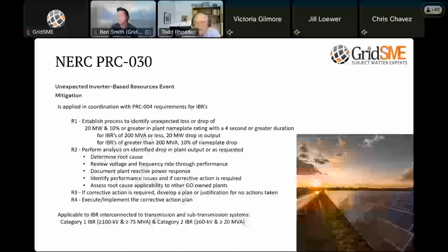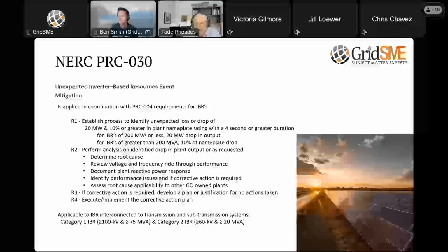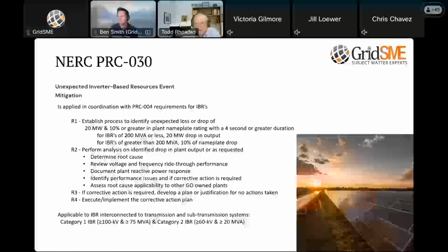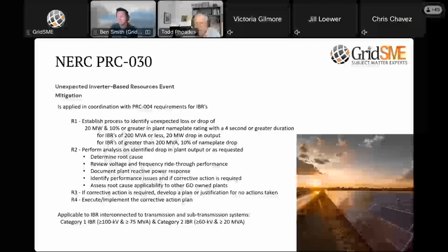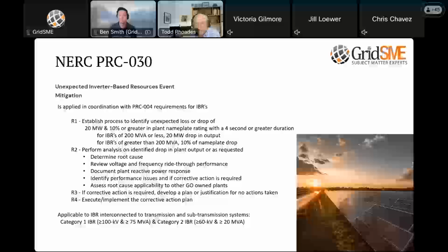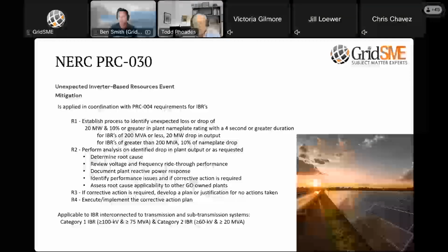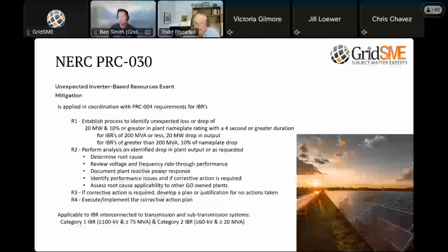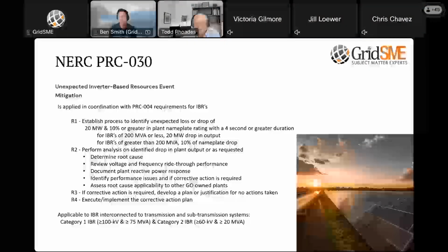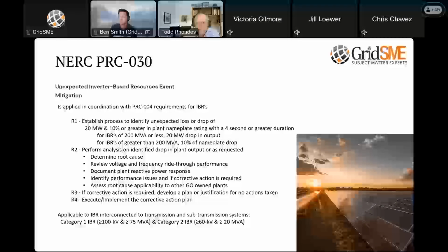So now we'll move over and talk about how do we monitor and what do we look for in terms of performance. So PRC 30 is looking at how does the plant respond to unexpected events. So we've seen a change in the system and the plant went into a response mode. So we'll take a look at that. But this works in coordination with PRC 4, which is a requirement that you look through your protection system of your substation to validate that your protection system operated and responded accordingly. So this is taking that a little further and looking at the outputs, not just the tripping aspects of your protection system, but the response aspects of your inverters also.